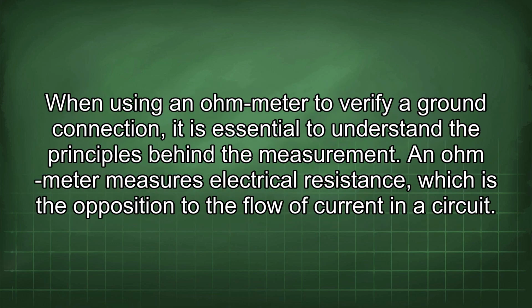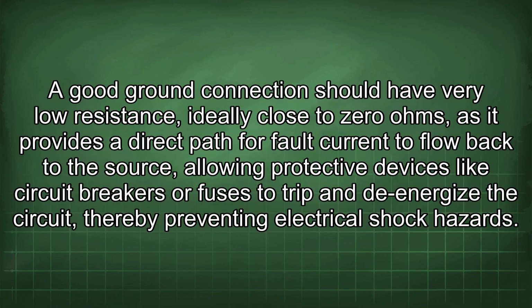When using an Ohm-Meter to verify a ground connection, it is essential to understand the principles behind the measurement. An Ohm-Meter measures electrical resistance, which is the opposition to the flow of current in a circuit. A good ground connection should have very low resistance, ideally close to 0 ohms, as it provides a direct path for fault current to flow back to the source, allowing protective devices like circuit breakers or fuses to trip and de-energize the circuit, thereby preventing electrical shock hazards.